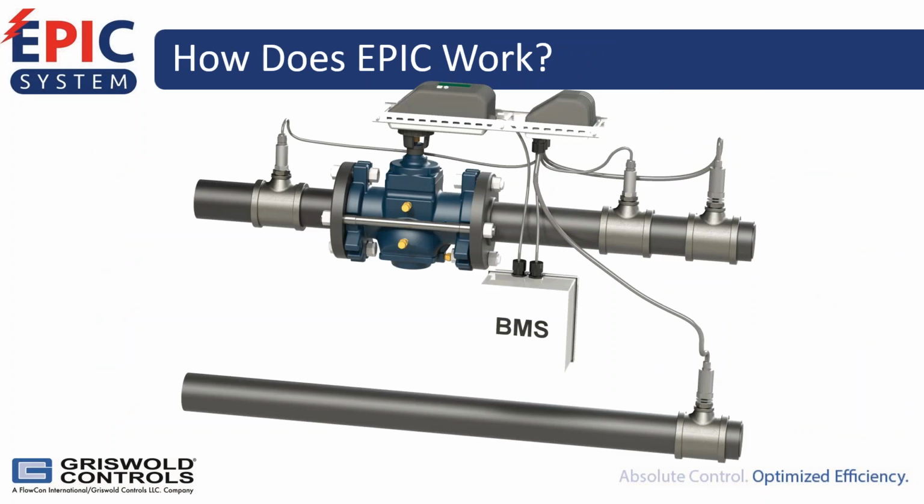So how does it actually work? Well, the simple answer is the EPIC system measures the energy usage while monitoring the coil performance to adjust the pressure-independent valve so that it can optimize that coil's performance. So the pressure-independent valve maintains the correct flow in spite of any pressure changes and guarantees that the flow only changes when there's a demand or a load requirement change, not when there's a pressure change.